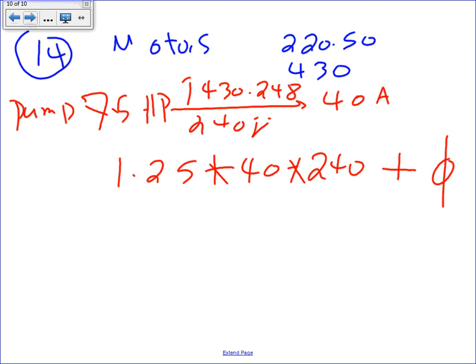When I put this one on YouTube, I got an email from a guy who said, Chad, why did you multiply the volt amp by 1.25? In reality, what's multiplied by 1.25 is the amps. But if you multiply the amps by 1.25 and you find the volt amp, you are multiplying the volt amp by it anyway. The reason why I multiply the volt amp is because I'm adding volt amp. I'm not adding amps. You can't add amps when you size the service because amps are different. 20 amps at 120 is completely different than 20 amps at 240. It's completely different than 20 amps at 240 three phase. But volt amp is volt amp. Apple is Apple. If I tell you a 5 horsepower, guys, take this.